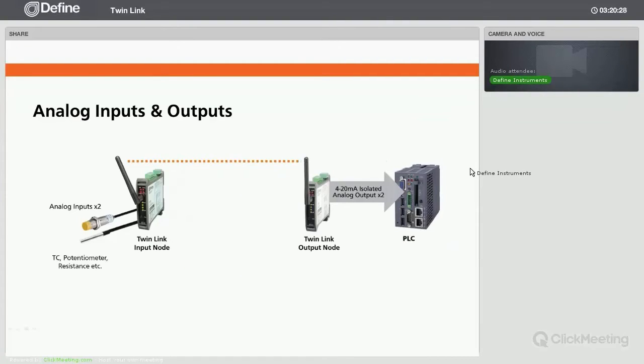So let's have a look at analog inputs and outputs in a bit more detail. Here is a simple example of a speed sensor and a temperature sensor which have been connected to the input node. The TwinLink input node measures a signal from both these sensors and transmits them to the output node. The output node then converts the signals to 4 to 20 milliamp and drives a PLC input.